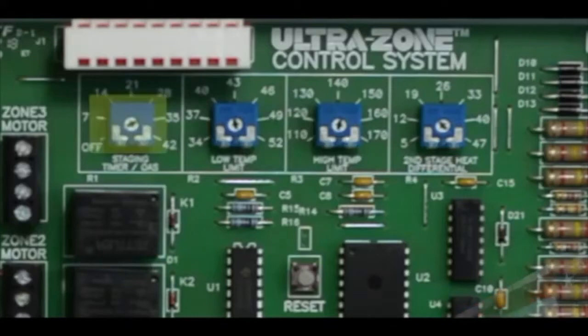First, as a timer for second and third stage operation. The time is set between 7 minutes and 42 minutes per stage. Second is an outside air temperature changeover setting due to temperature, 7 degrees to 42 degrees. Perfect for dual fuel operation and second stage heating operation.